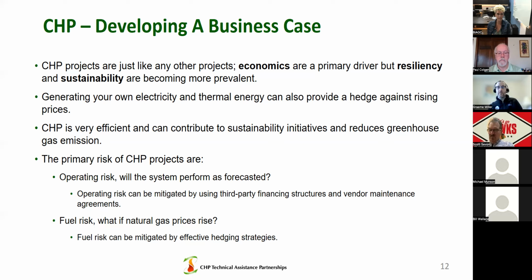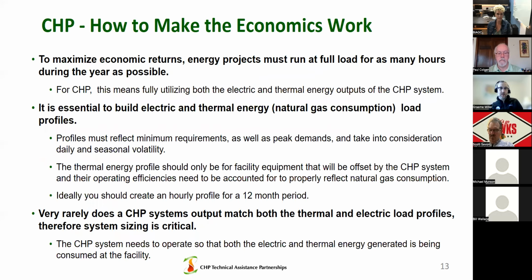So, making the economics work for CHP projects: to maximize economic returns, energy projects must run at full load for as many hours during the year as possible. As mentioned, this equipment comes at a significant capital expense, and you're only saving money when it's operating. So you want to size the equipment such that it can run as near to 24/7 as possible.